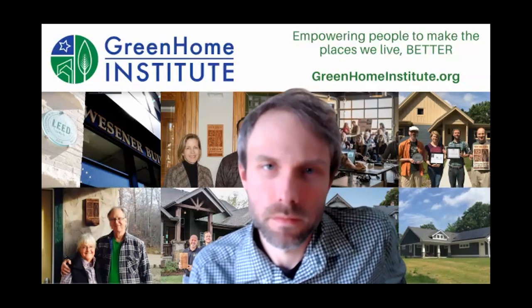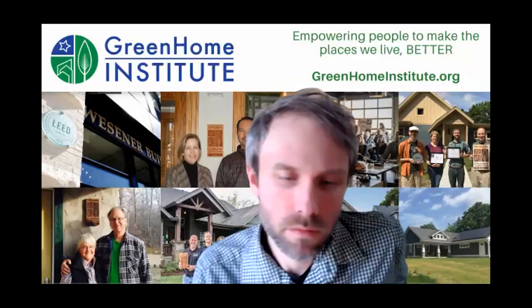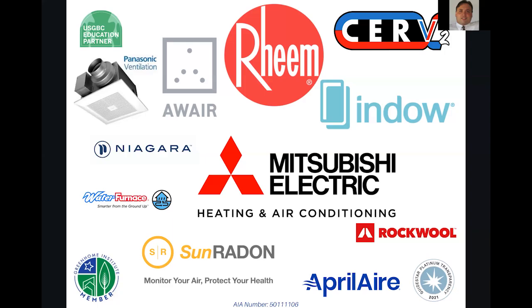Yeah, Mike, you probably have more data on cost. Some of this is highly variable, depending on how these are being applied, whether it's piecemeal applications with all these components we talked about, or a skid application. That's certainly more costly up front. It also depends on what space you have for storage versus recovery or heat pump output, and the number of heat pumps. So there's a lot of factors involved. I would say you're probably in the 3 to 5 times range of what a conventional system costs up front in many cases. But where this is really geared is these electrification markets, where you're forced to move natural gas away from the end user. The utilities are going to start taking over the use of natural gas for peaking plants in combination with more renewables to clean up the grid. And where gas isn't available and your only options are electric or heat pump technology, that's really where the savings comes into play. It's not uncommon to see a 50% reduction in operating cost in those scenarios against an all electric solution.